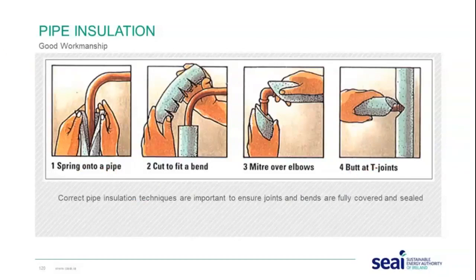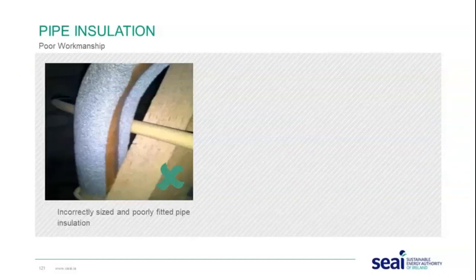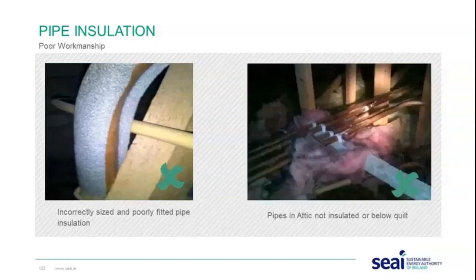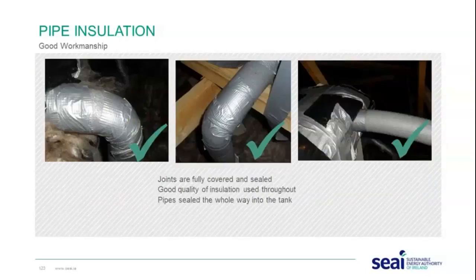Further poor workmanship examples include incorrectly sized pipe insulation and pipes in the attic that are not insulated or are left below the quilt. If pipes are running less than 300 millimetres from the ceiling, it is possible to insulate them by running the quilt insulation over the pipes. Good workmanship means joints are fully covered and sealed, quality insulation is used throughout, and pipes are sealed all the way into the tank.